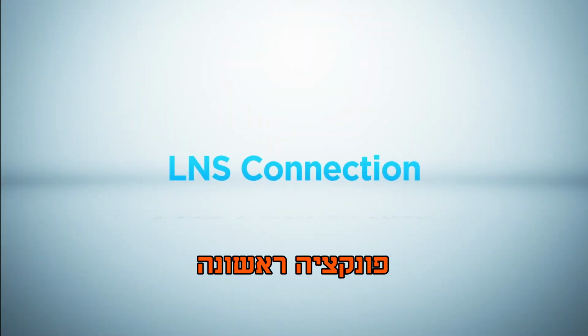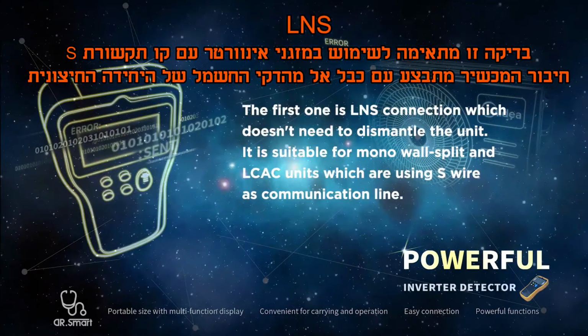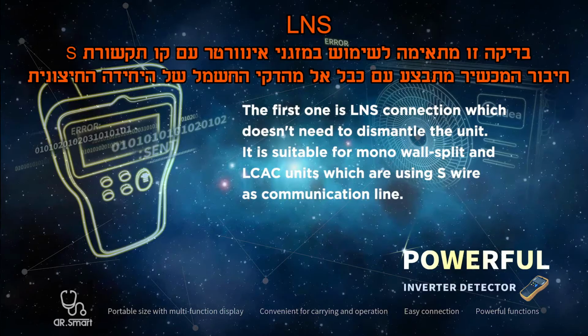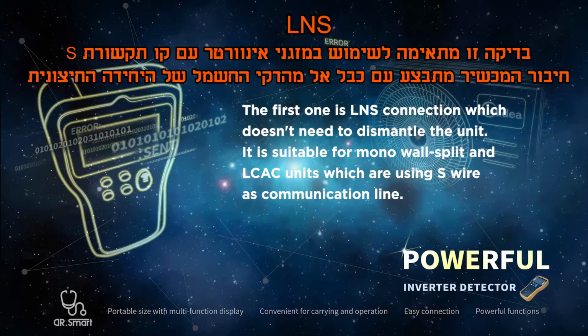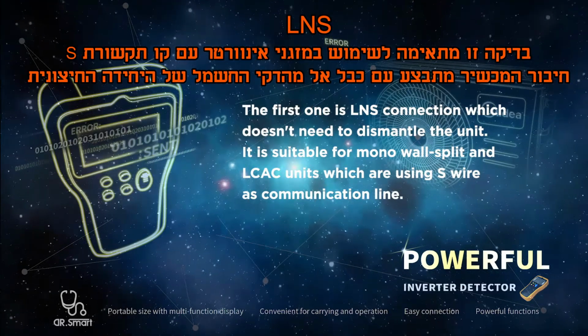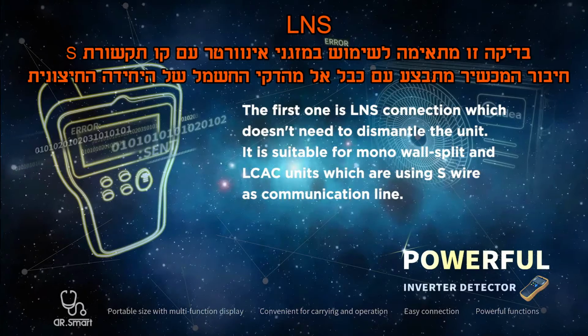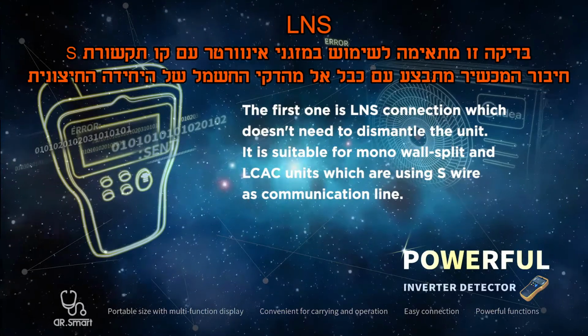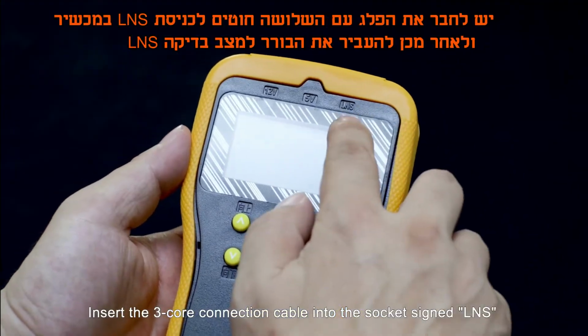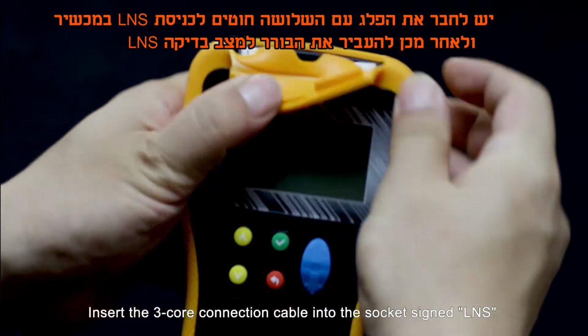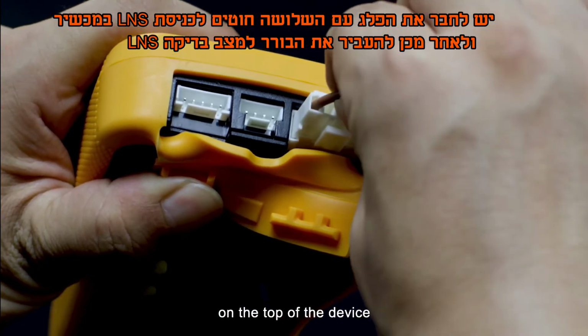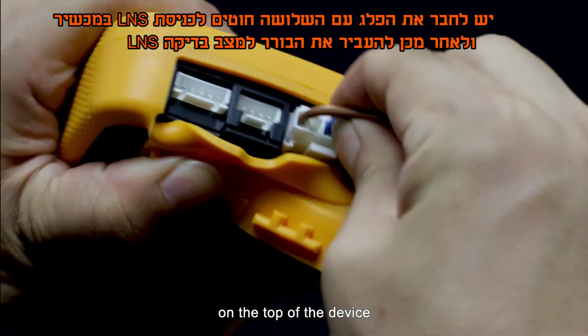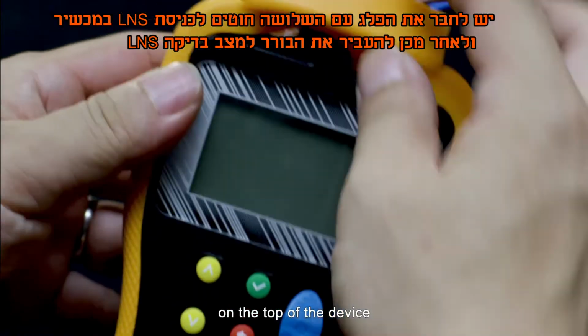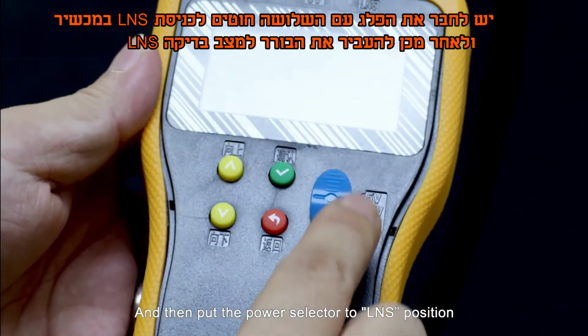LNS connection. The first one is LNS connection, which doesn't need to dismantle the unit. It is suitable for mono wall split and light commercial units which are using S-wire as communication line. Insert the 3-core connection cable into the socket signed LNS on the top of the device. And then put the power selector to LNS position.